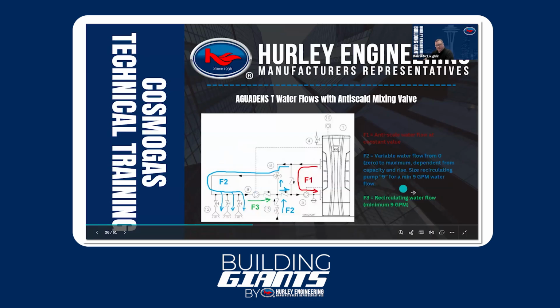And that's critical as well, because here we're suggesting 9 GPM, and that's what generally you need to keep enough flow through this 3-way valve so that it can accurately mix the water and keep the temperature correct. I will say that's a rule of thumb. You should always look, this 3-way valve is not sold with the CosmoGas. That would be sold separately and independently. So look at what equipment you have on site. Look at your manufacturer's recommendations. They might need more or less, but I wouldn't go below 9 GPM. But if they require more flow to accurately mix the water, then you can certainly do that as well.